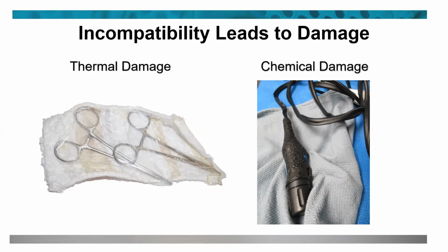Now, some of them may come with a dual way of doing it. You may see that you can sterilize it with heat or you can put it into a chemical sterilization process. So you're going to want to do what is best. But again, you want to make sure that you follow the IFU for that to make sure you're getting the correct way.